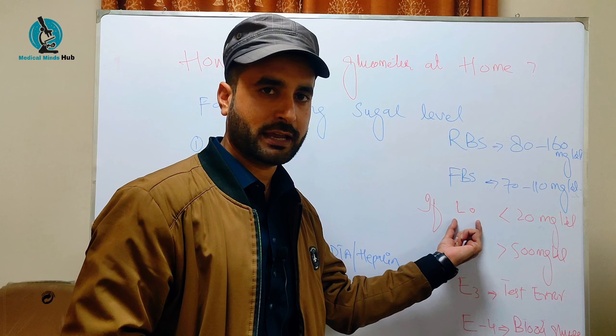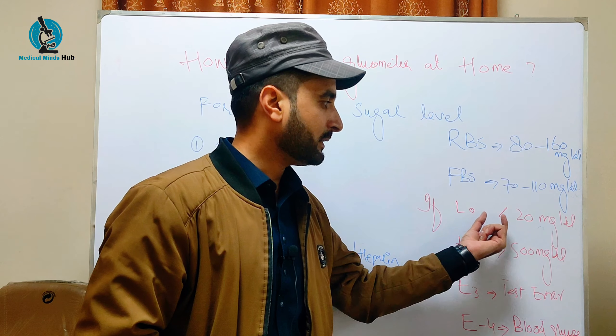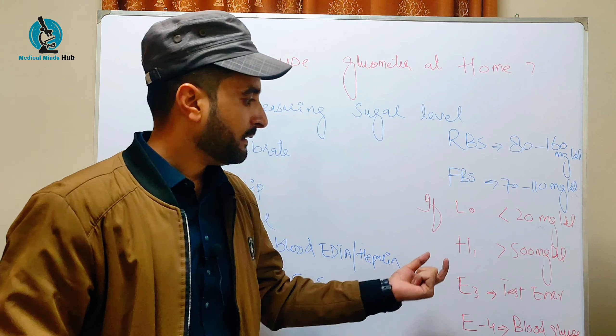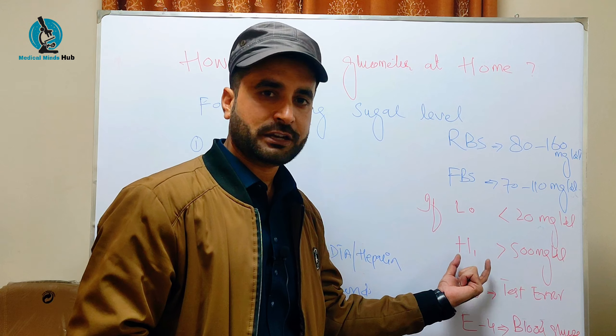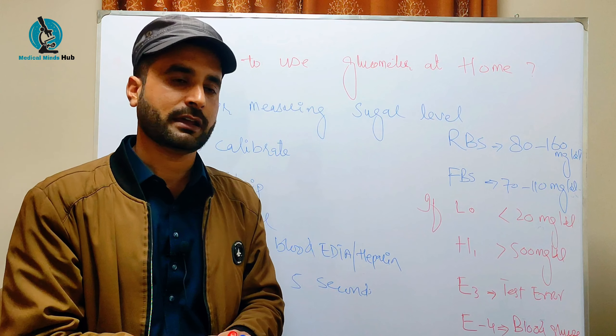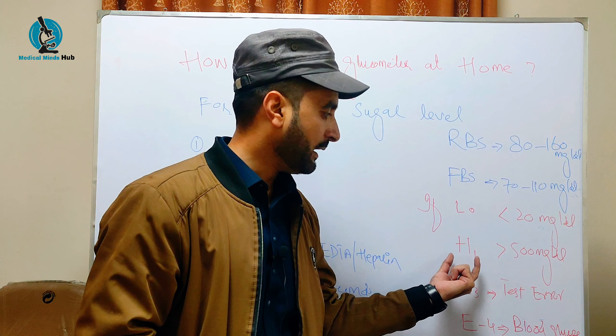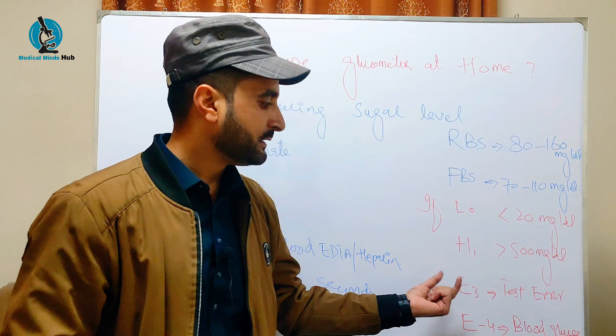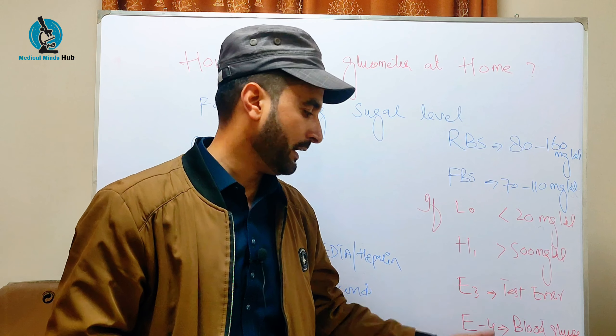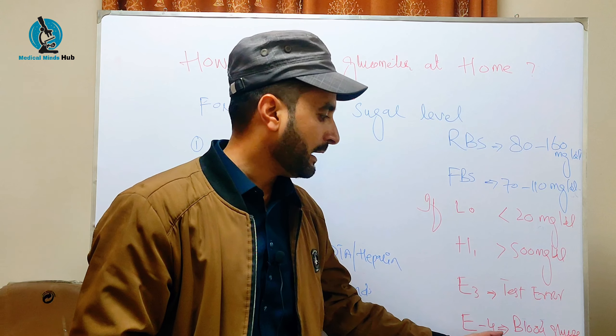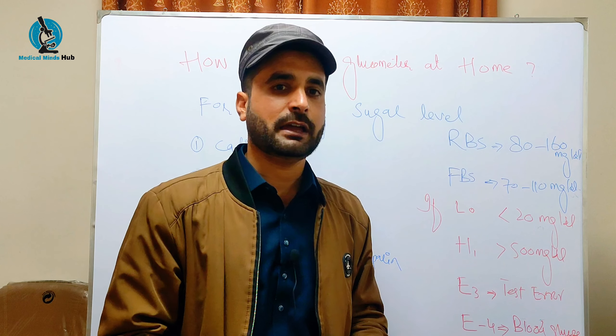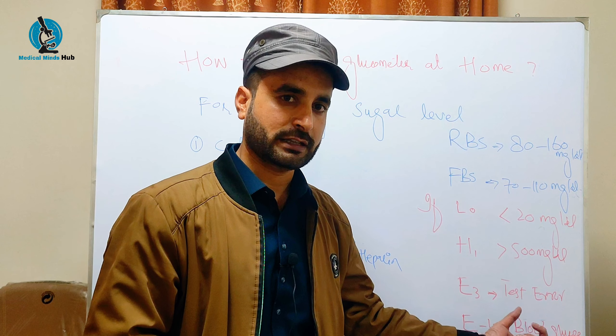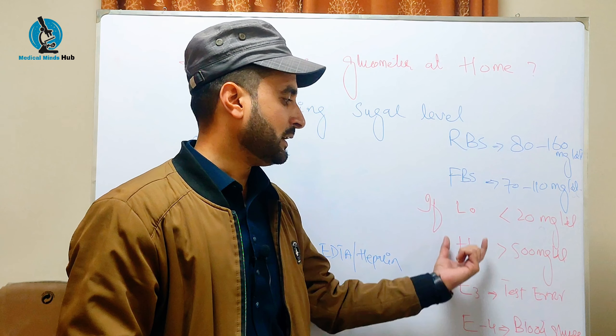When using the Glucometer, the display LO is very important — it means the patient's sugar level is below 20 mg per dL, which is an emergency. HI means blood sugar is above 500 mg per dL. A test error on the screen also indicates a problem with the reading.